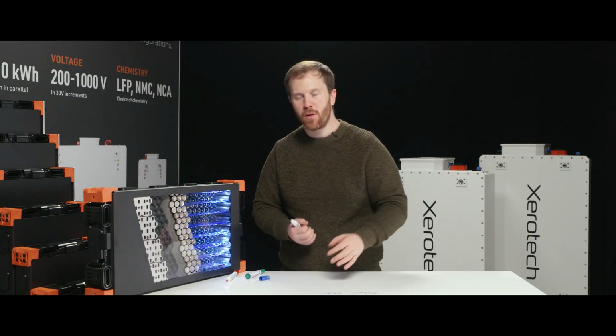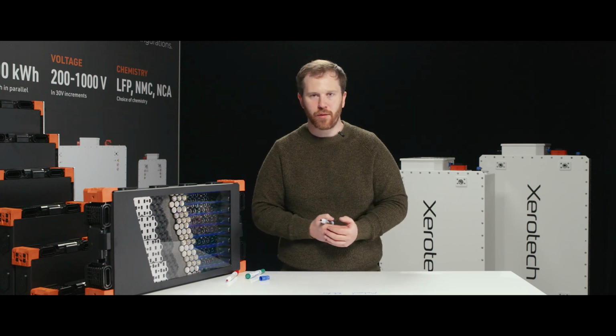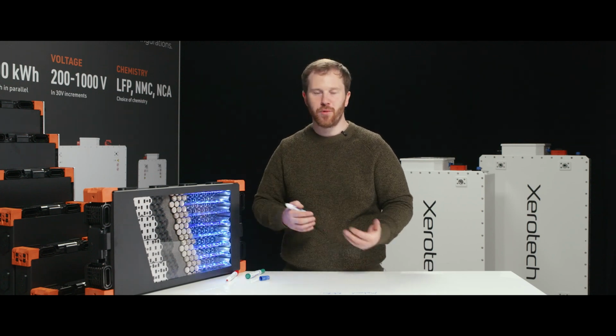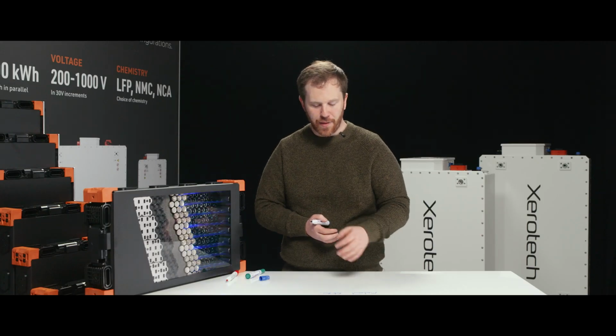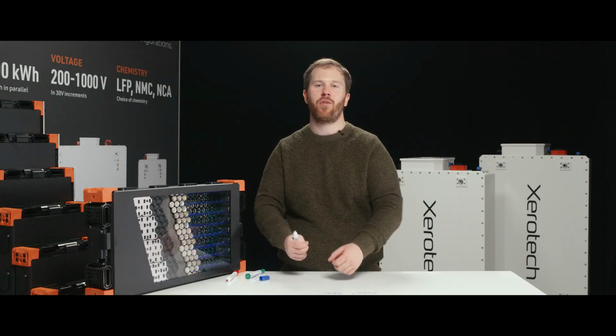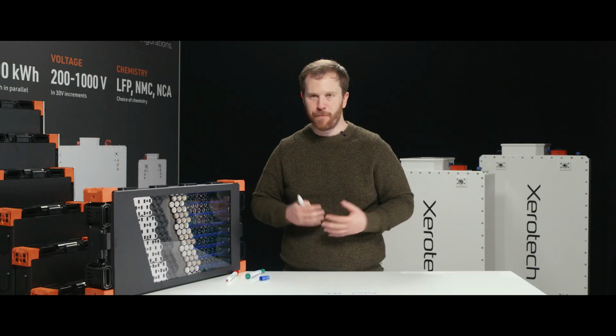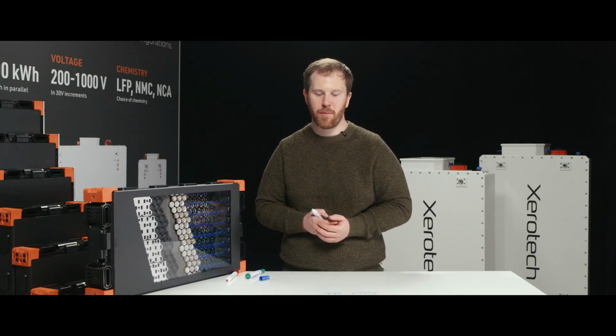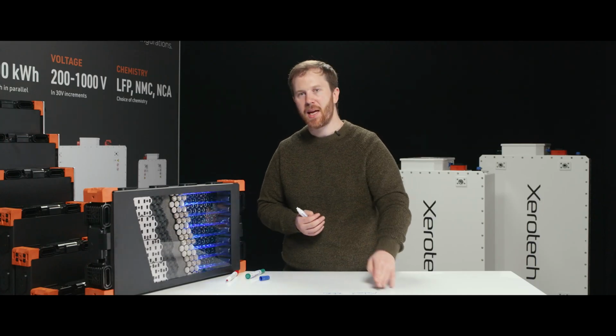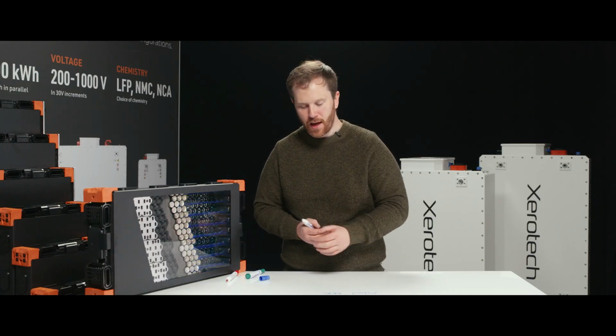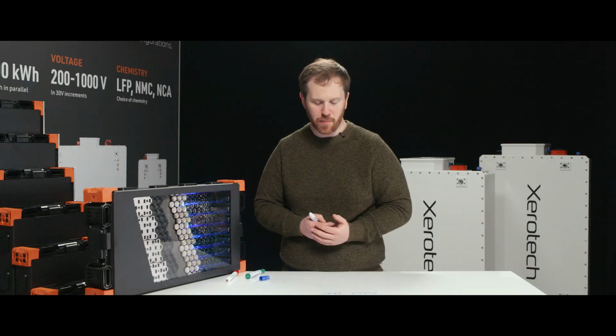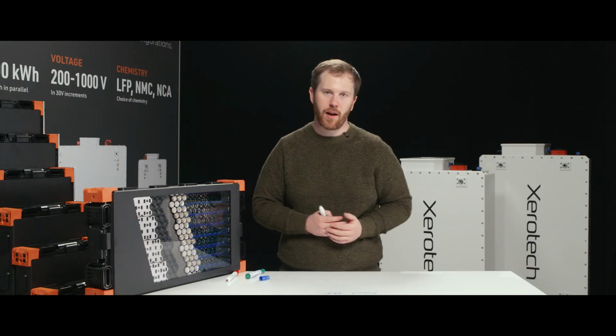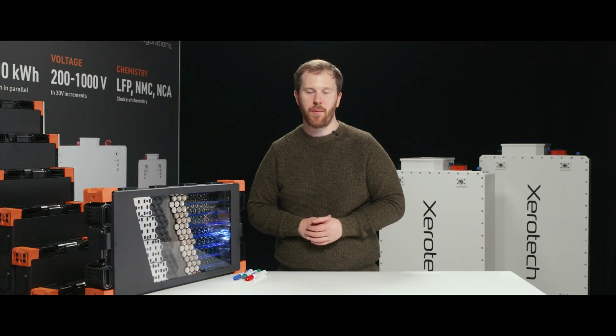When it comes to the cooling system, you need to be worried about over-pressurizing the cooling system. Putting too much flow rate through it or too strong of a pump can damage cooling systems. And then on the mechanical perspective, that you don't put excessive shock, vibration, and force into the battery packs that could cause mechanical damage. So there's many ways to mitigate these through both active and passive methods, and their protection systems are incredibly important to ensure the safe and long-term reliability of a battery pack. So that brings us to the end of our deep dive into safety systems inside of battery packs, battery modules, and some of the considerations to safely use and operate battery packs.